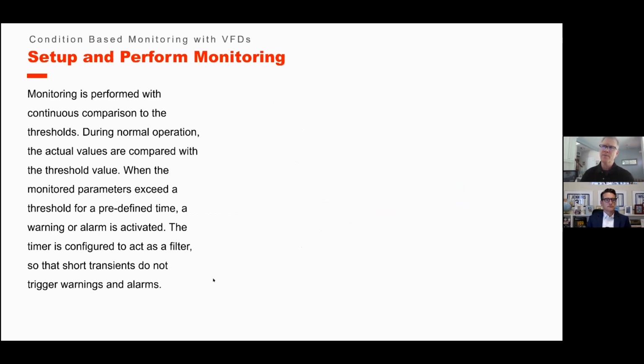So the monitoring is performed continuously, comparing those thresholds to the baseline. During a normal operation, the actual values are compared to the threshold. When those monitored values or parameters exceed the threshold by a predefined time, which you do set in the software, you'll get a warning or an alarm. The warning you'll get too, of course, and the alarm will trip the drive. So you have to be careful if you're in a production run and you're setting those alarms. You have to be pretty confident in what you're doing to set the alarm in that case, but it's a very useful tool.